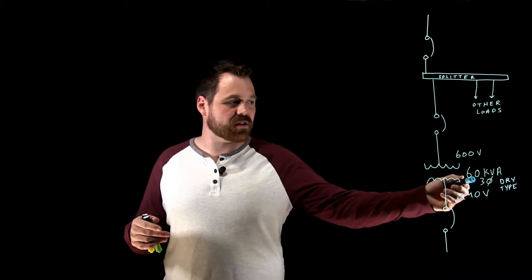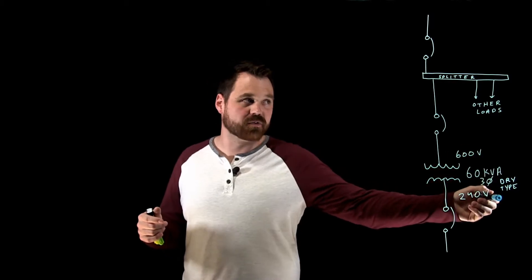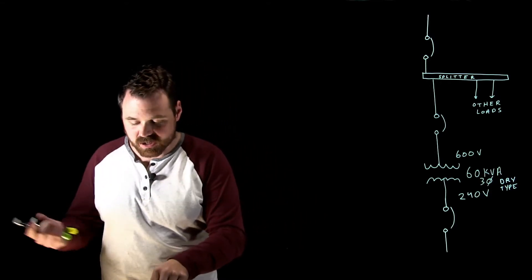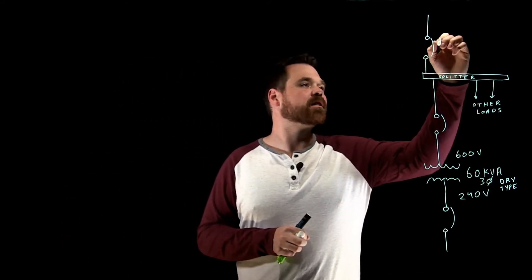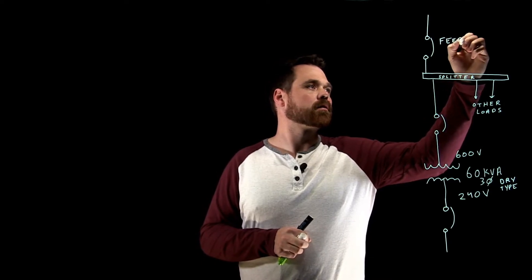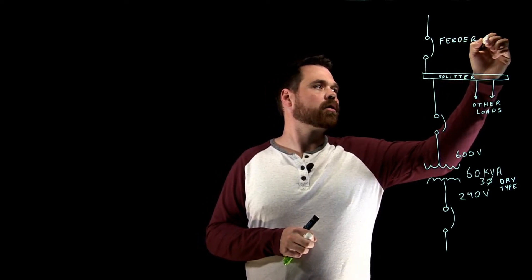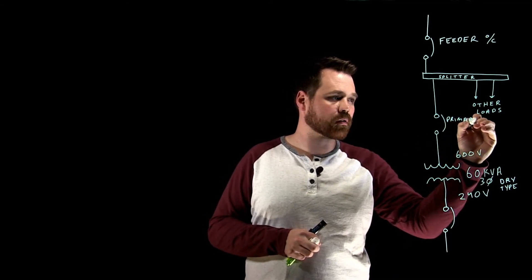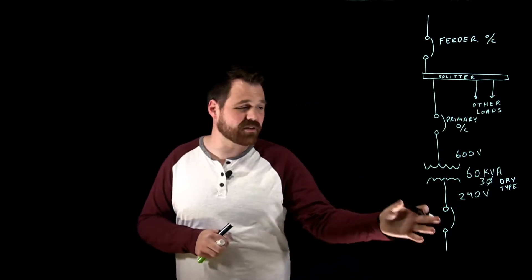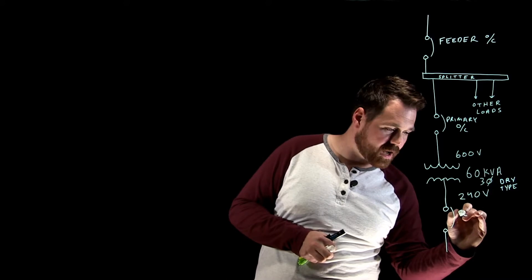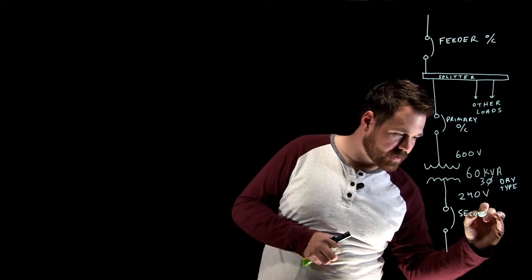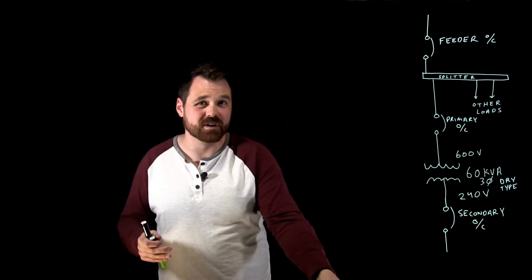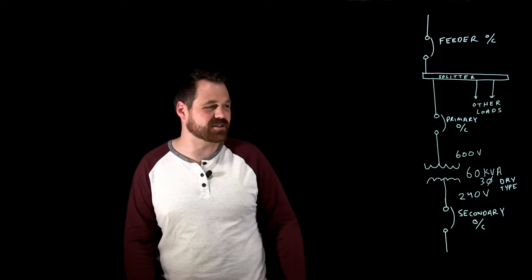I've got as an example the 60 kVA three phase dry type 600 to 240 volt transformer and I've got it drawn into a system where I have a main, a feeder OC up here, this is our primary OC, and then down here I've drawn in a secondary OC but you're not always going to install these secondary OCs.